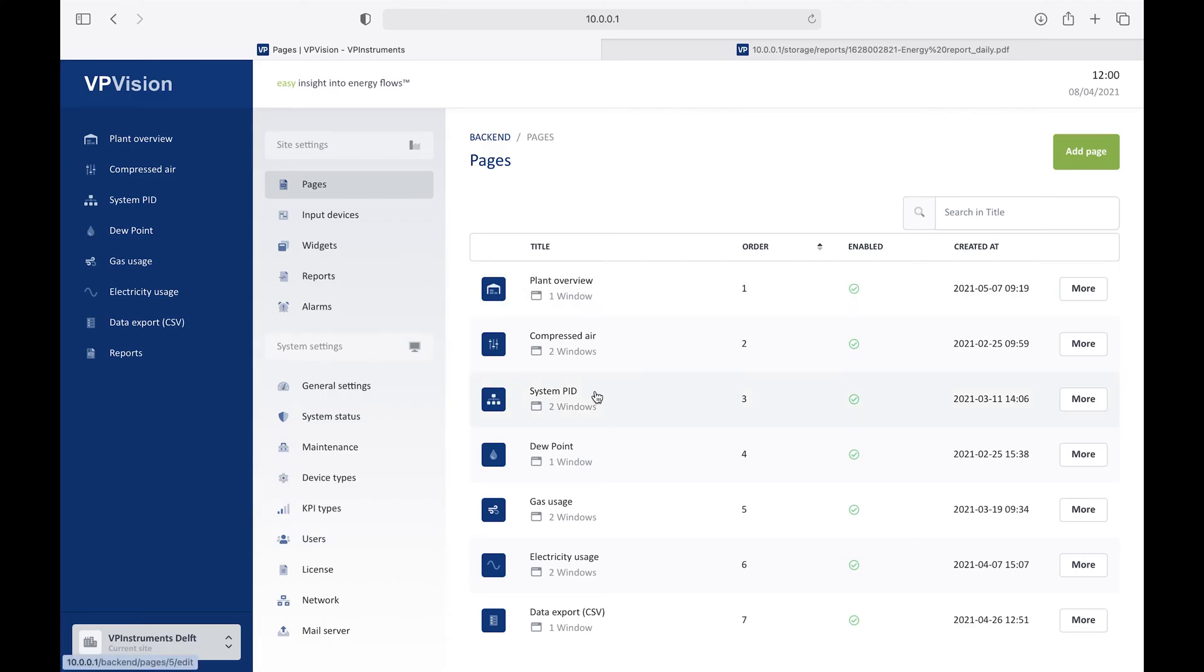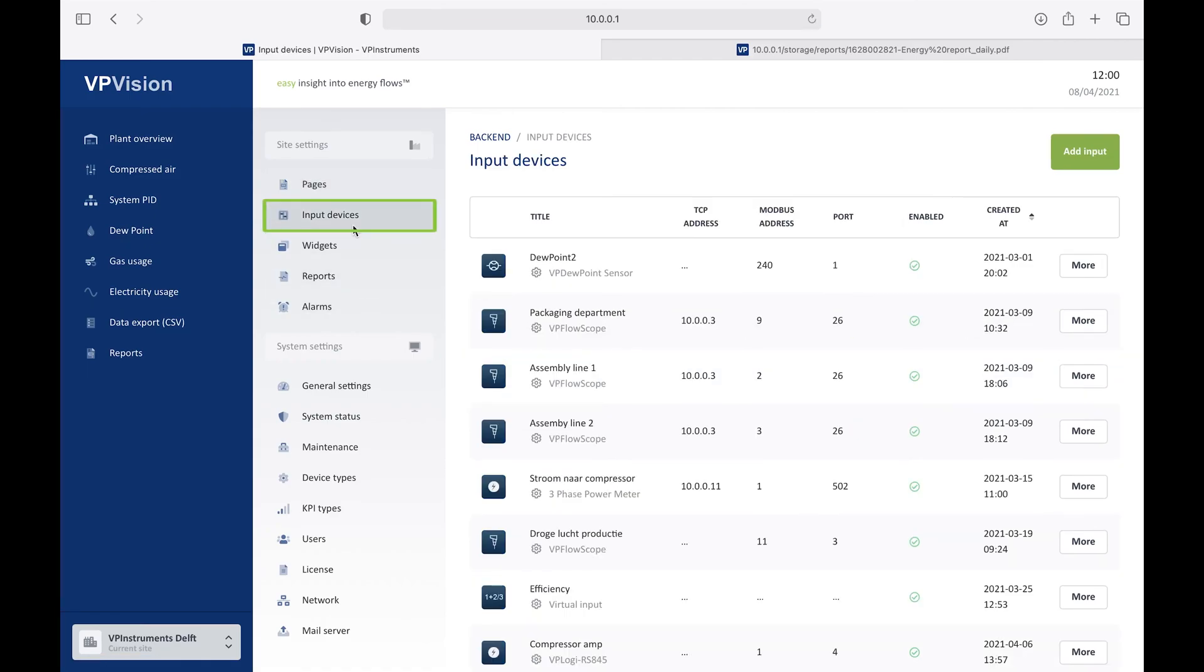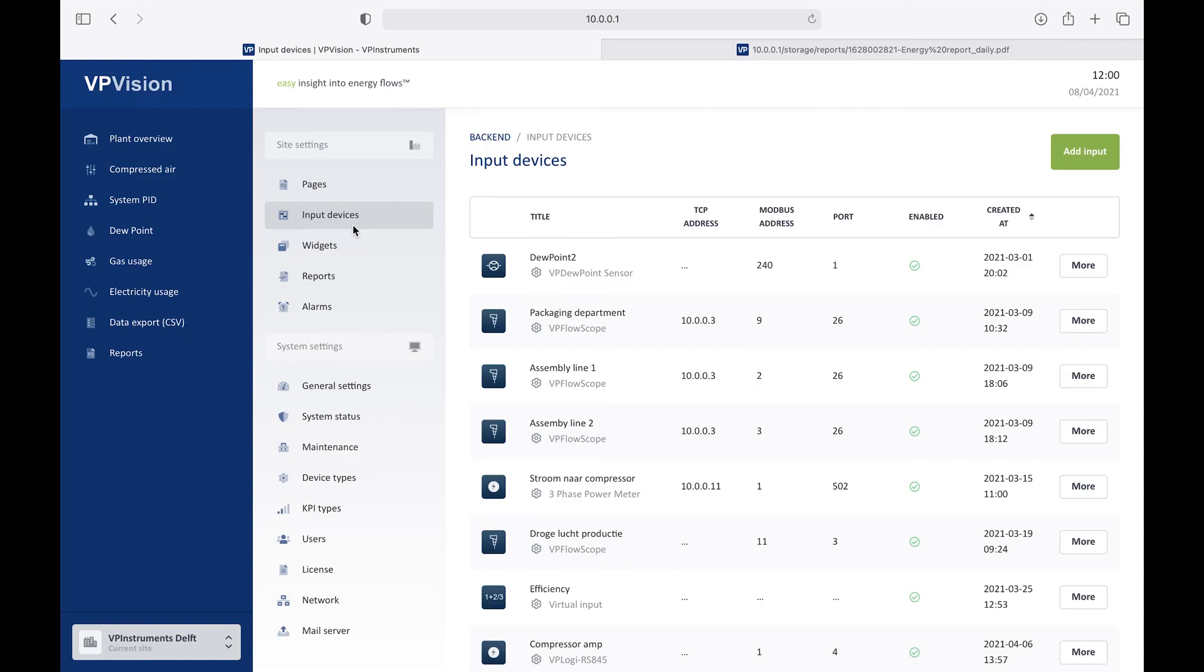I want to highlight a few of those features. First of all, there's the input devices, and what's nice about VPVision is that it's hardware agnostic. You can basically interface it with any device which offers an analog, a pulse, or a Modbus signal. In this way, VPVision is basically brand neutral. You can connect sensors, and even you can connect panels from compressors if they offer a Modbus output, or a Modbus over Ethernet output.